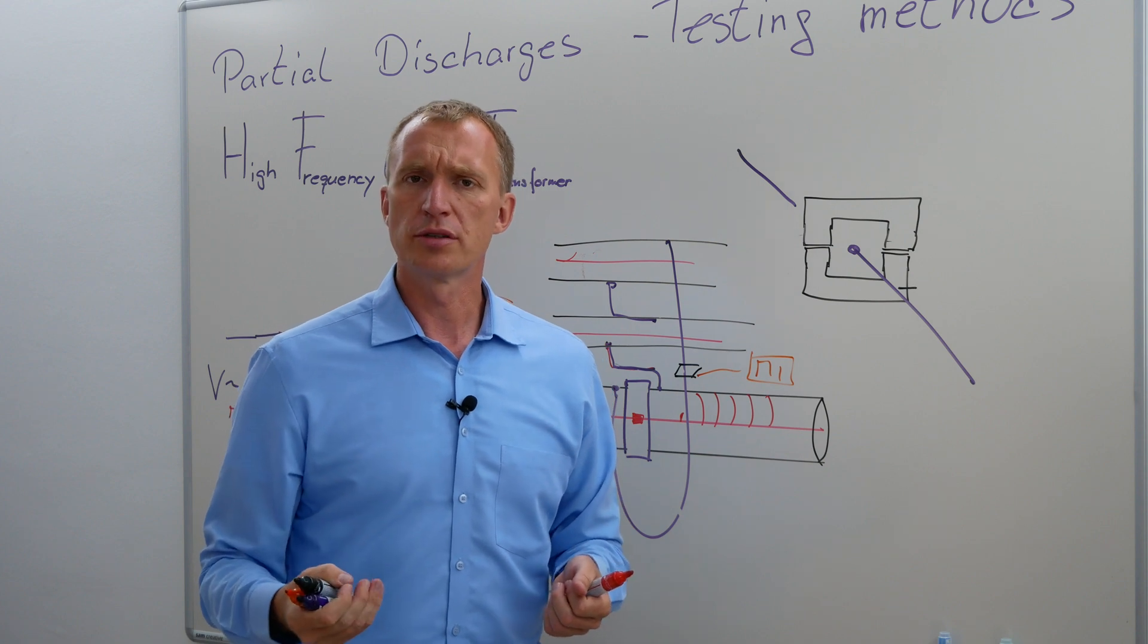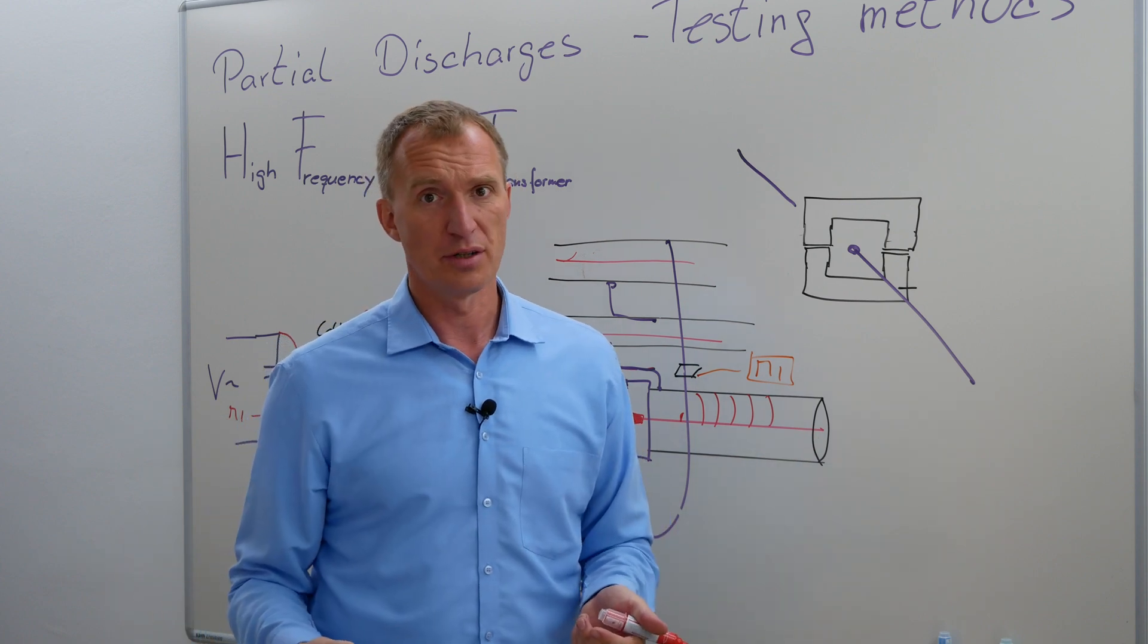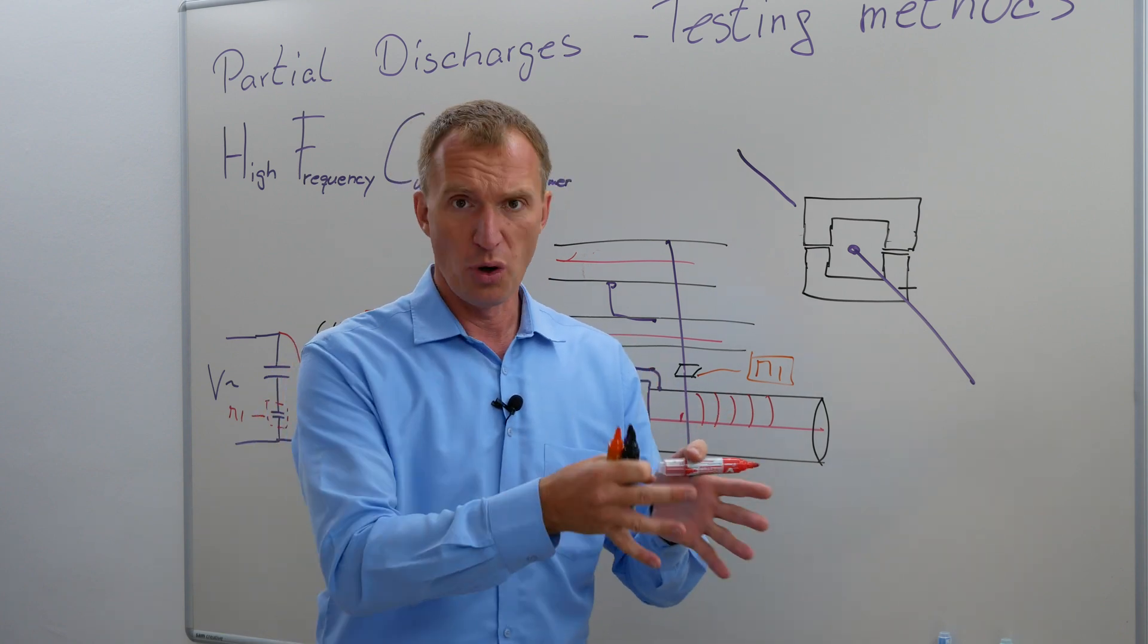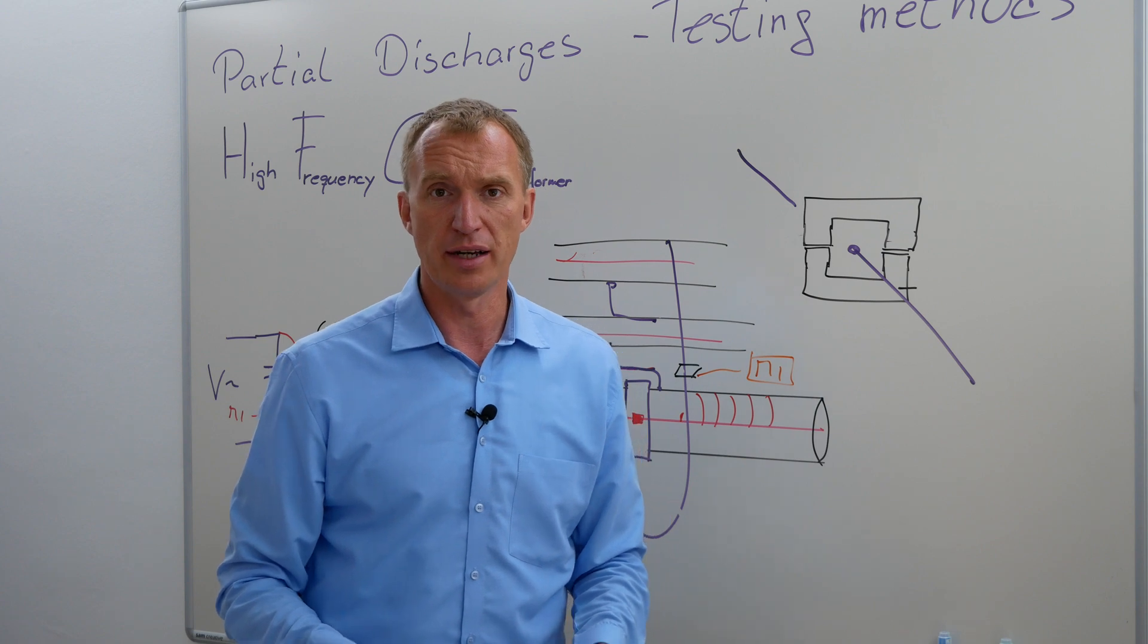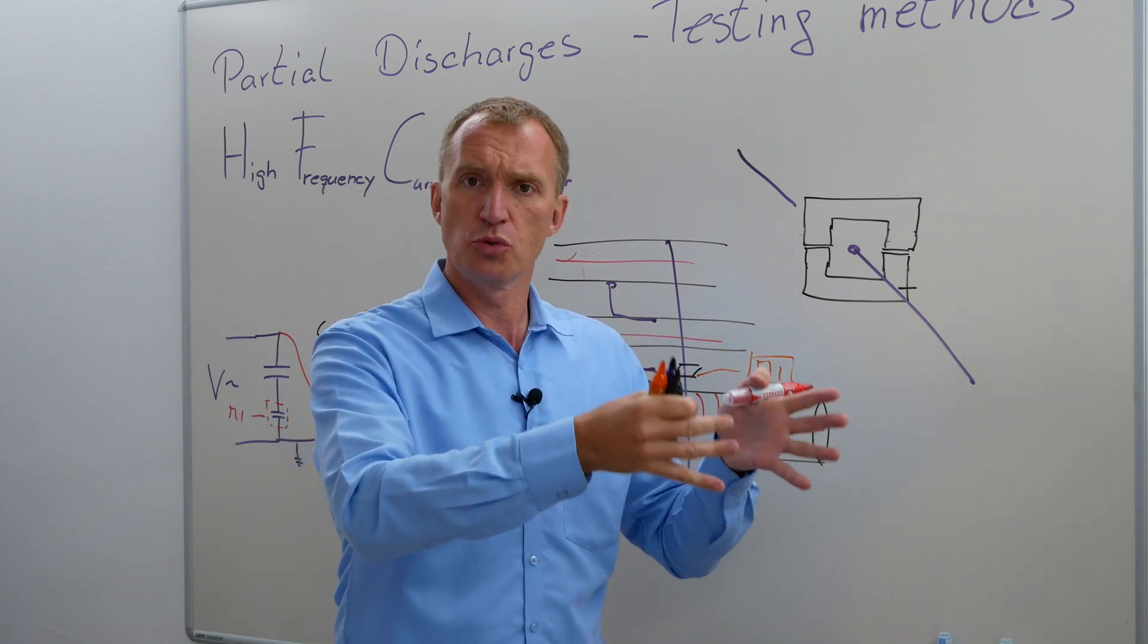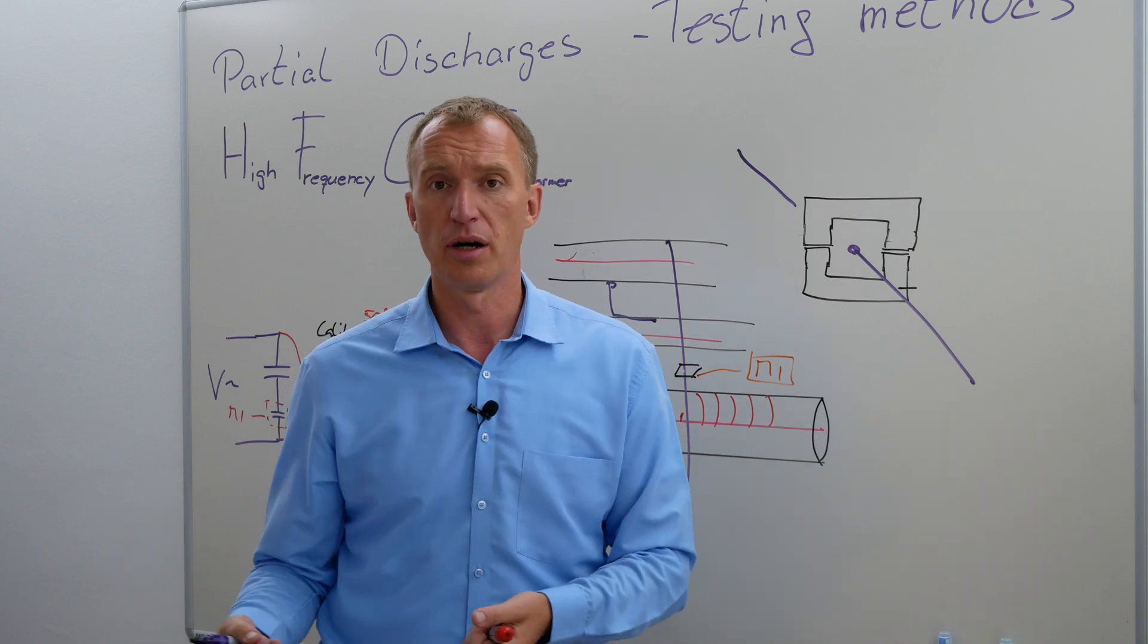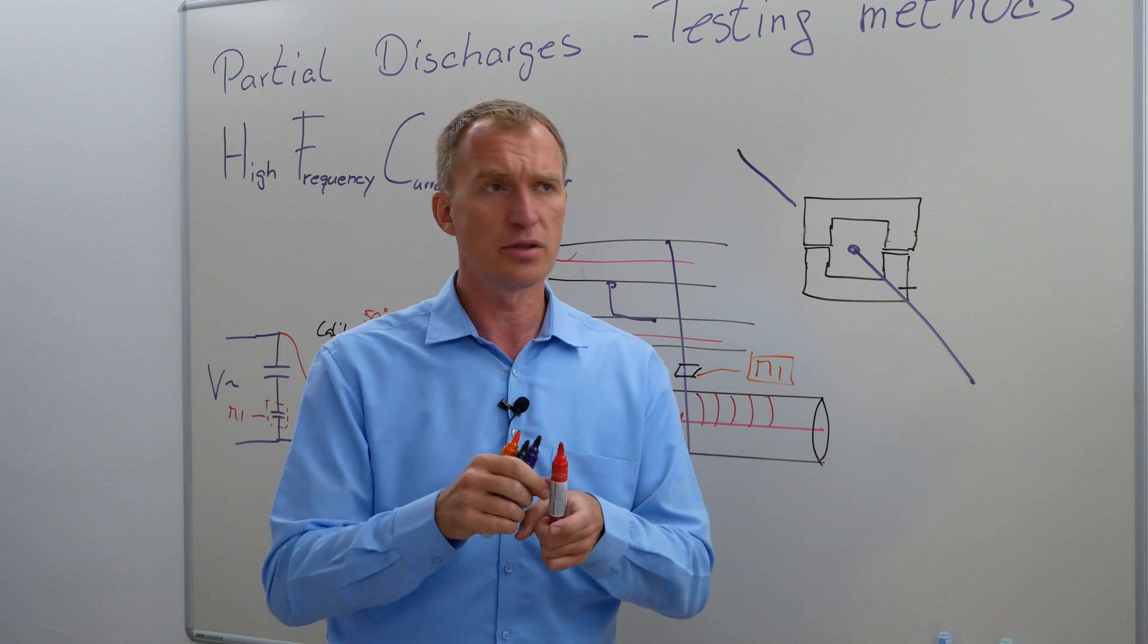This being said, you could do this on medium voltage cables as well. You could do this on other places as well. You could do this if you do an online measurement. Because if you do an online measurement, the idea of online measurement is that you do not take the cable offline. And there are people in this world, they told me, you know what, it is easier for me to hire a killer for my mother-in-law than to actually take one of these very important high voltage cables offline. And the question is which one is more enjoyable. But let's not get into something like that here. Sometimes it's possible to do an online measurement on a cable which is operating with nominal voltage, do a measurement, and if you find something, then definitely you have reasons to take the cable offline and do a proper offline cable measurement system. Because we remember that it has something to do with partial discharge inception voltage and extinction voltage. We got a video for that.